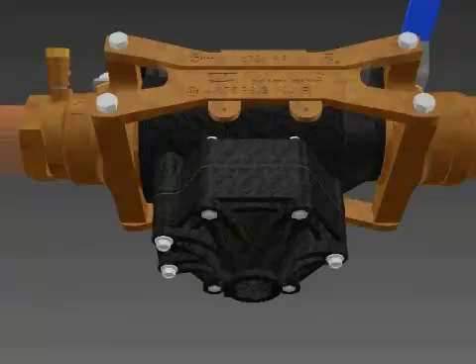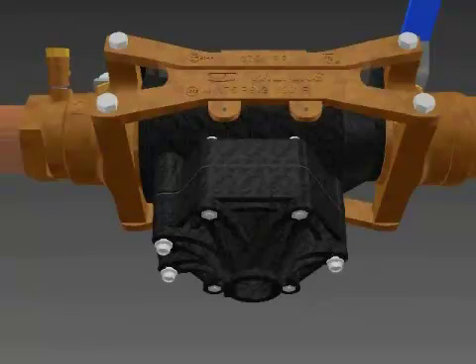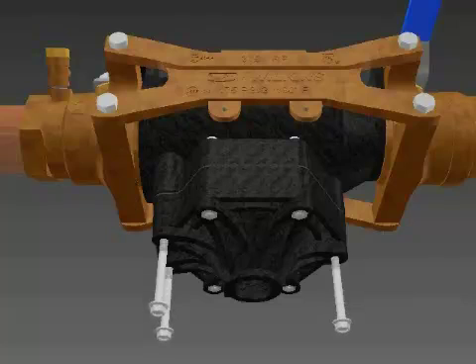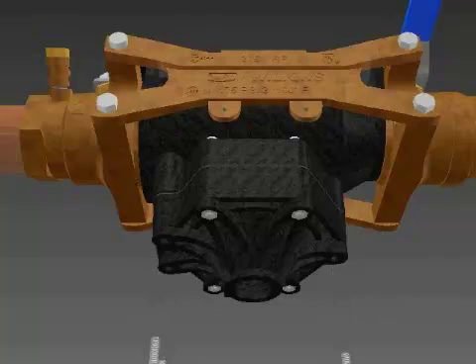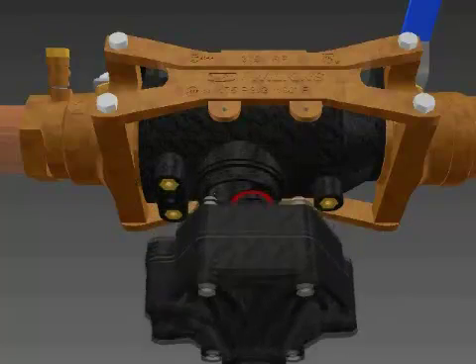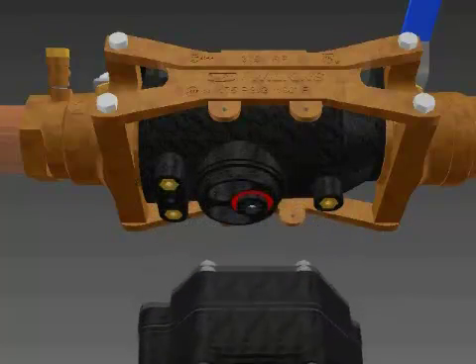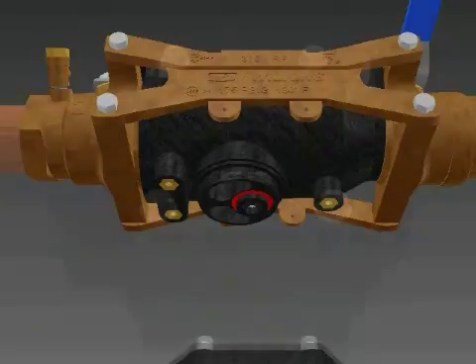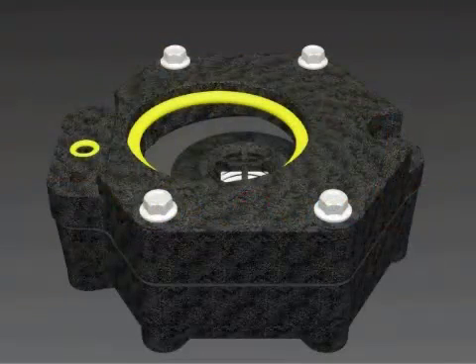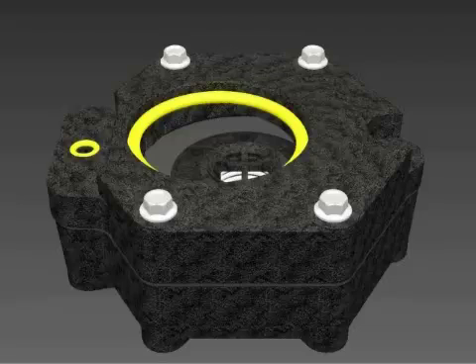Next, you will unscrew the four bolts on the bottom of the relief valve cover counter-clockwise. Pull down and wiggle the relief valve assembly to remove it from the housing. Be careful not to lose the large or small O-rings that might stick to the bottom of the check housing or the relief valve assembly.